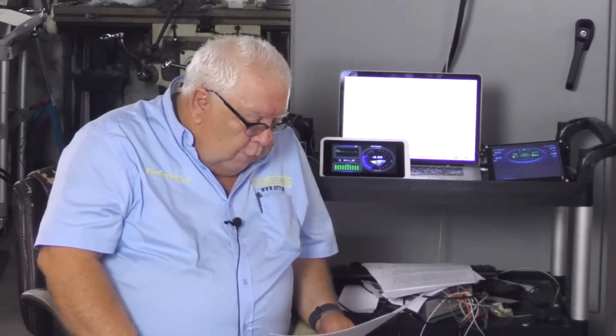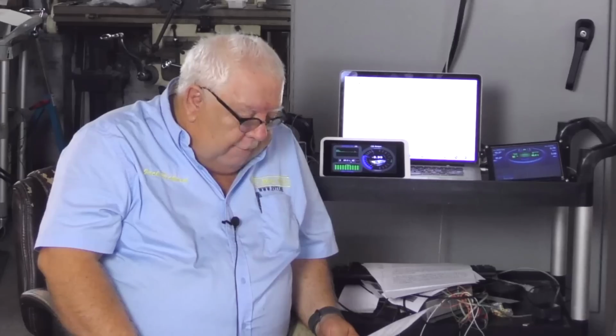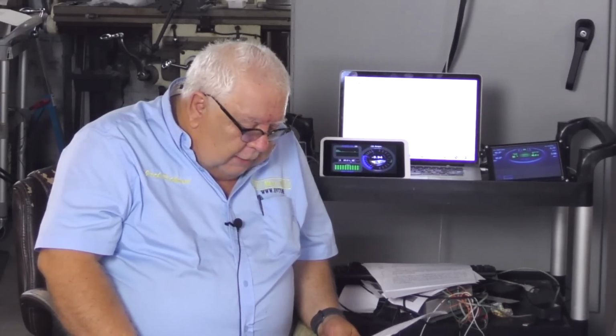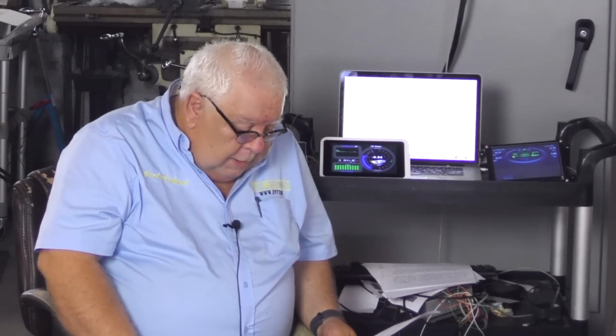We had disconnected the battery pack on a temperature alarm, which is exactly what it's supposed to do, but I had it at a fairly high level, like 55 C. I cleared the alarms and reset the system, and we resumed charging, and it worked fine for about 4 hours.